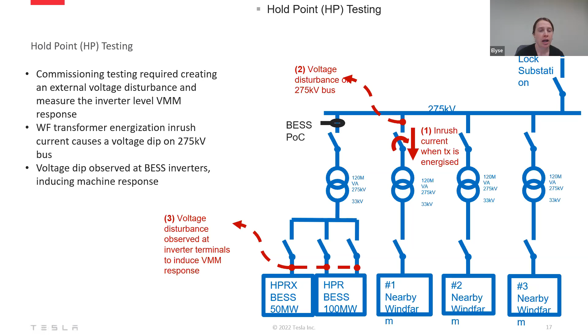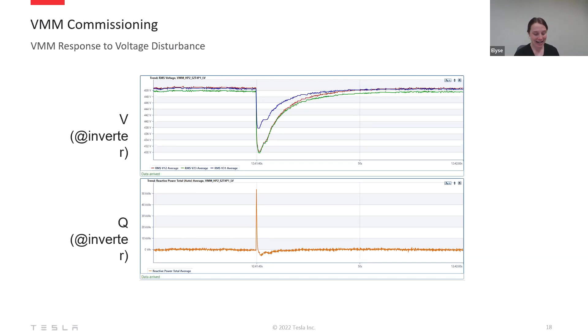On the next slide, this is the exciting bit for us, which is that we observed that voltage dip. There's a very quick voltage dip at the inverter terminals, and the corresponding reactive current output of the inverters, which is evidence again of the machine mode response in the reactive power responding to clean the voltage waveform. So this is what it's all about, really. Next slide.